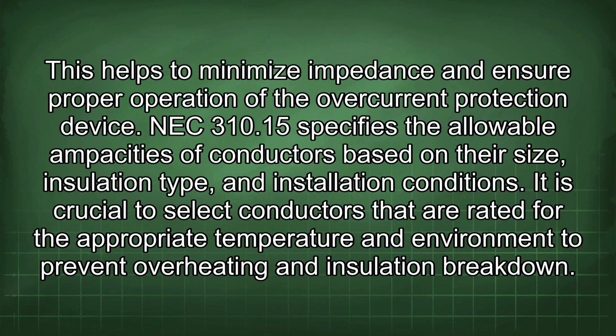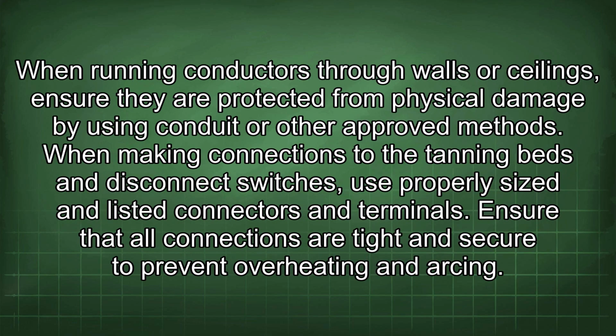NEC 310.15 specifies the allowable ampacities of conductors based on their size, insulation type, and installation conditions. It is crucial to select conductors that are rated for the appropriate temperature and environment to prevent overheating and insulation breakdown. When running conductors through walls or ceilings, ensure they are protected from physical damage by using conduit or other approved methods.